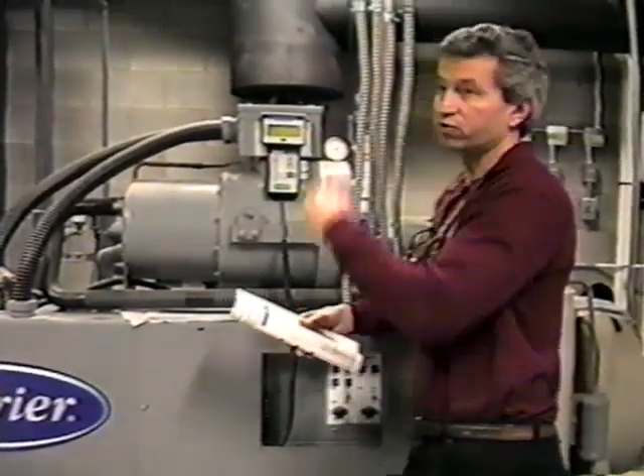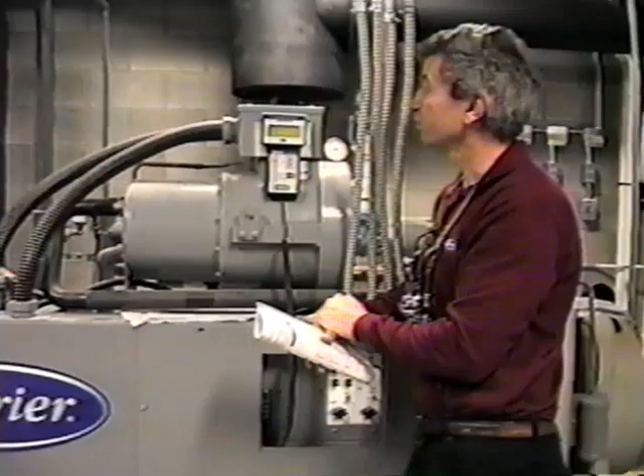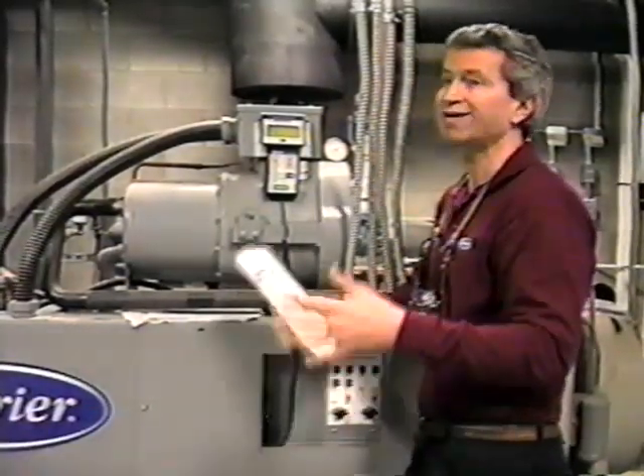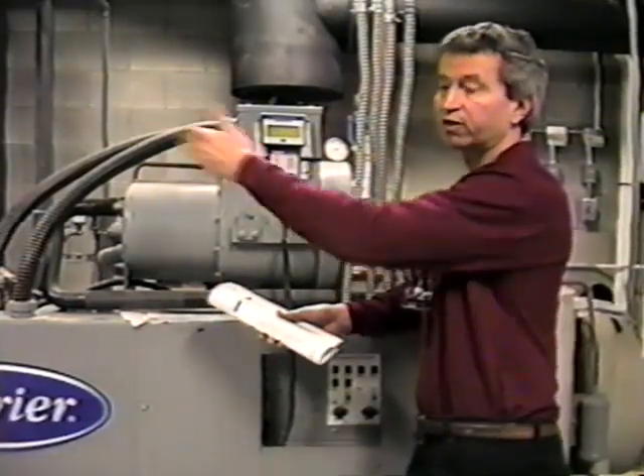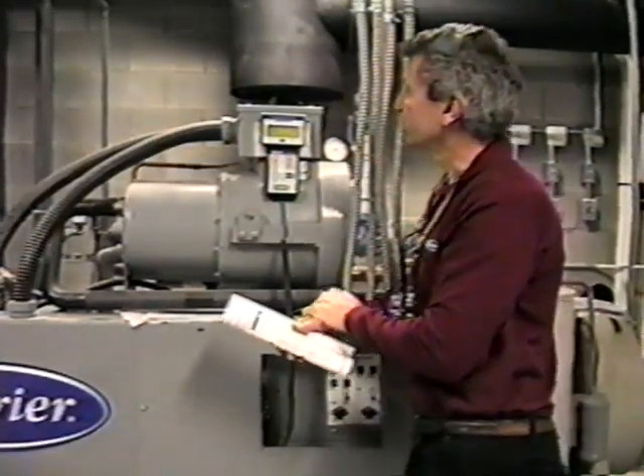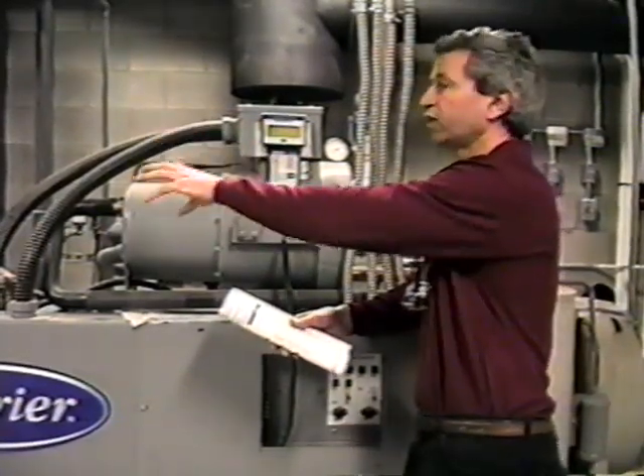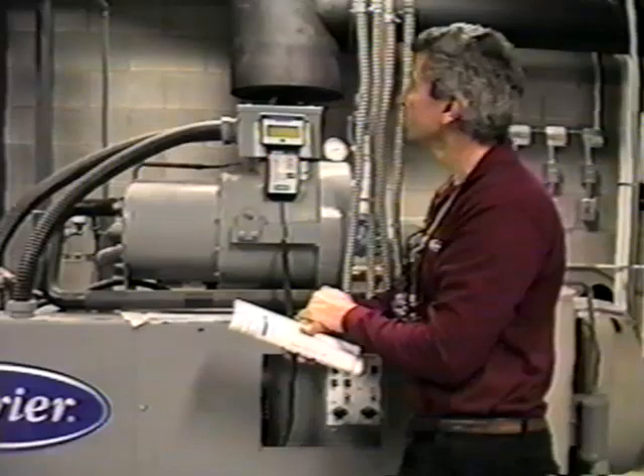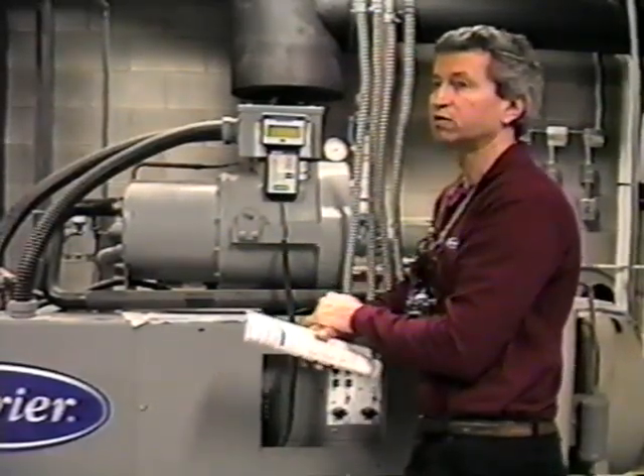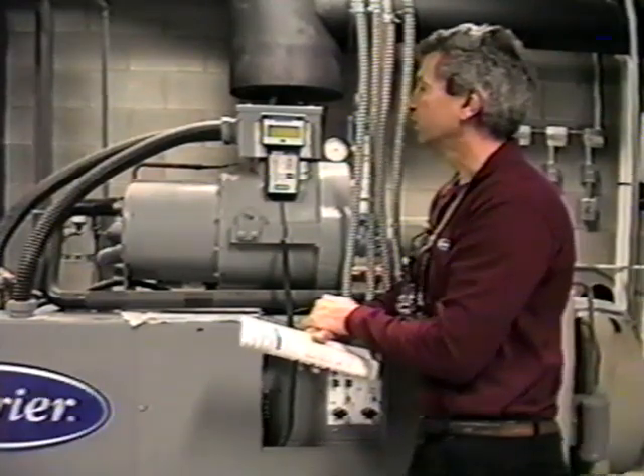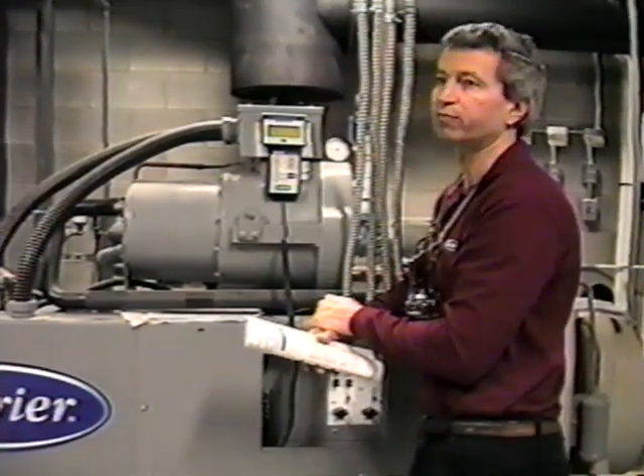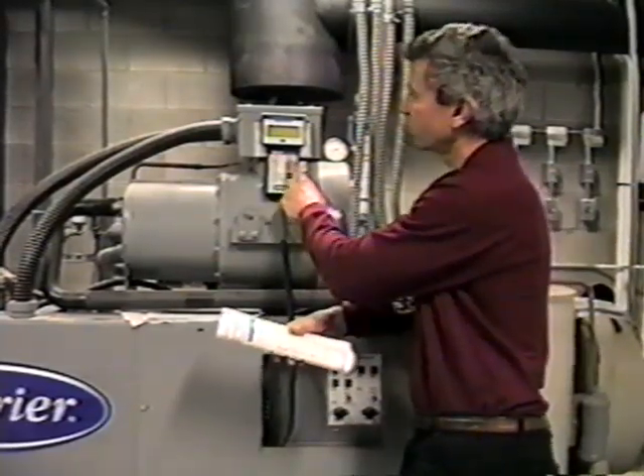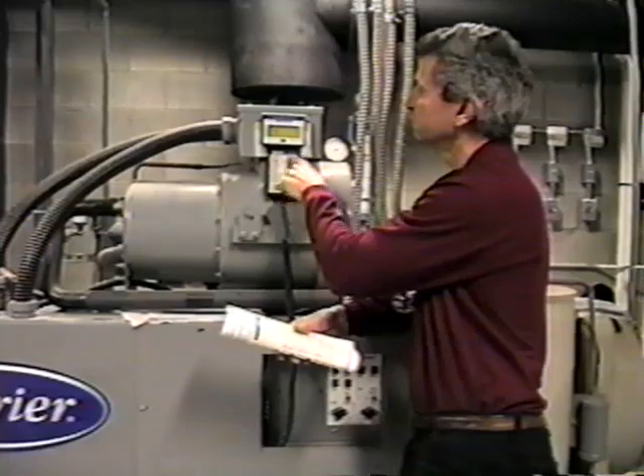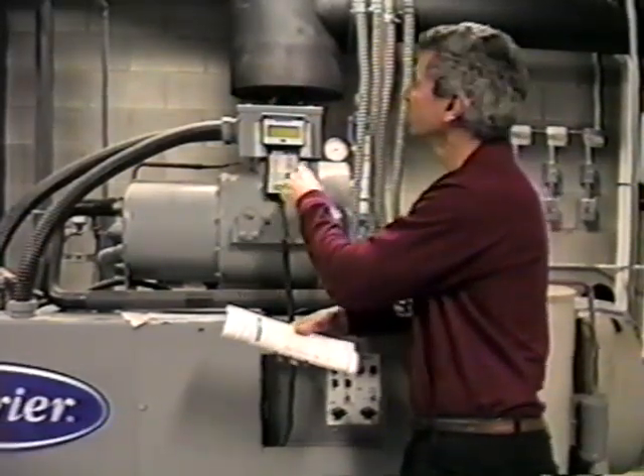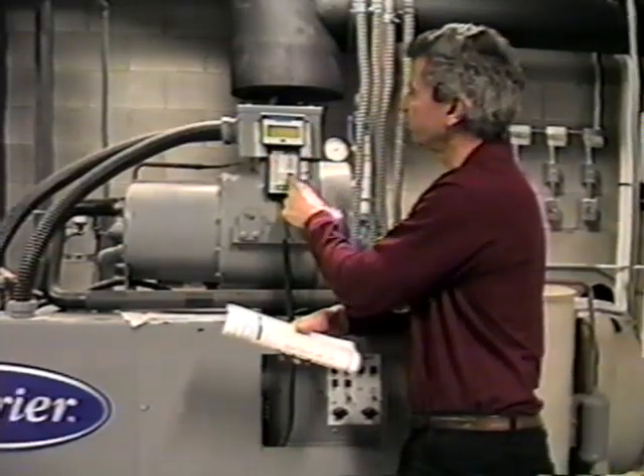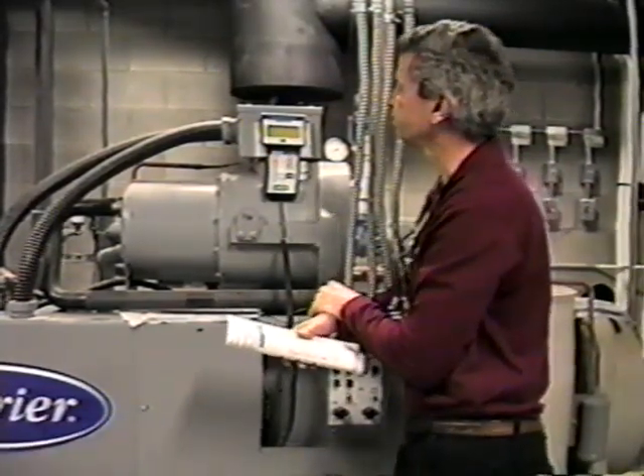Now you see you've got three different sub-menus, sub-modes at that point. You have unit, which are going to be all your unit temperatures, anything common to both A and B circuit. And you have circuit A, so any temperatures that are dedicated only to circuit A will be on that menu. And then circuit B, all circuit B temperatures. Let's say you wanted to check your discharge temperature on circuit B. You can either scroll up or down. This is a continuous menu, so you can go up or down. In this case, it'd be shorter to go up, so I went up, circuit B. Again, hit enter when you get to an item you want.